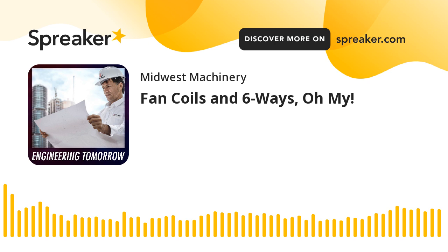Something coming down the pike is a consolidation of the valving. The 6-way valve is raising a lot of interest because it takes away the complexity of adding a solenoid valve, a shutoff valve, a control valve, an autoflow valve, and a proportional valve as separate valving. All of this could potentially be one valve.